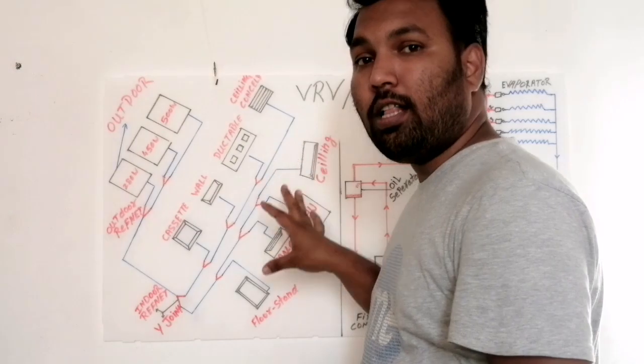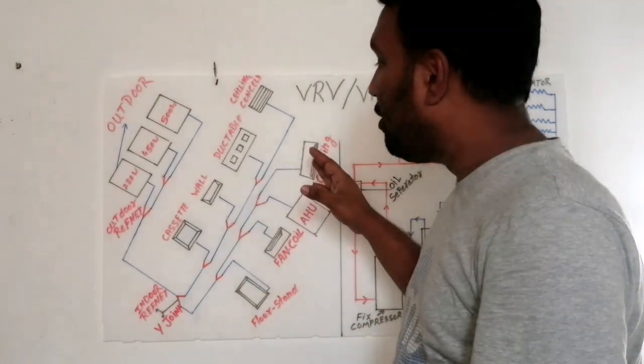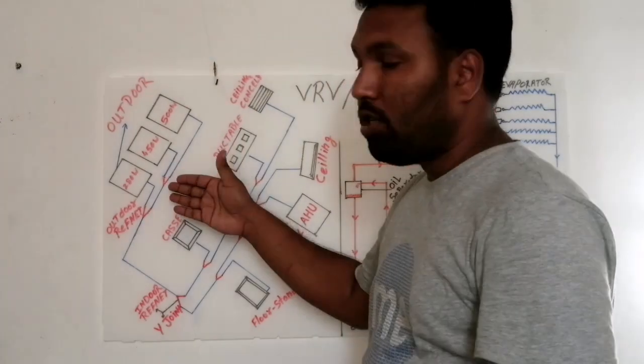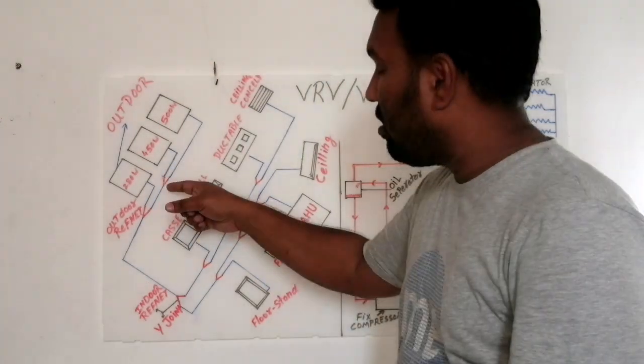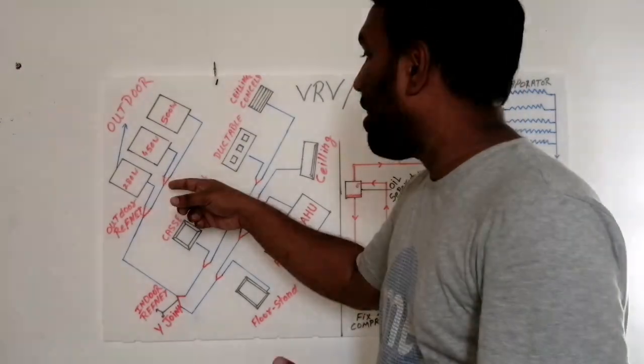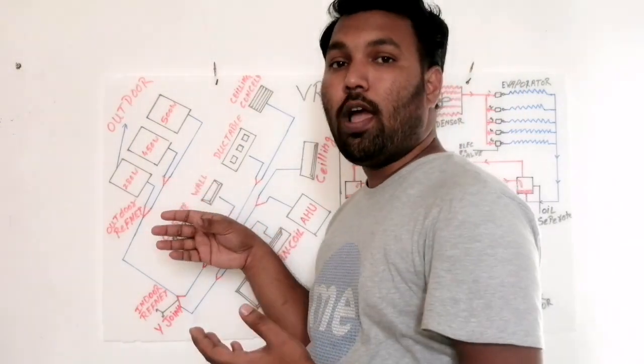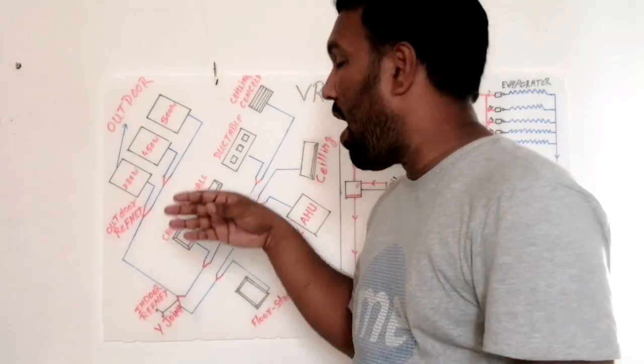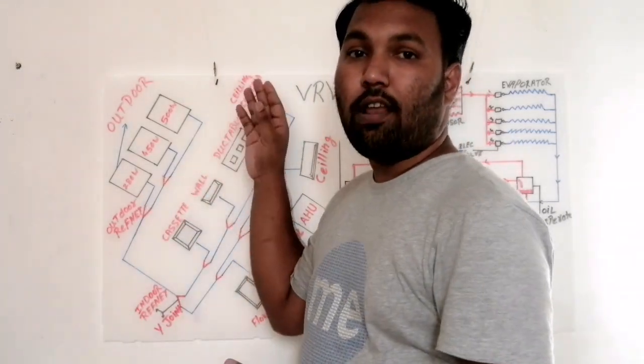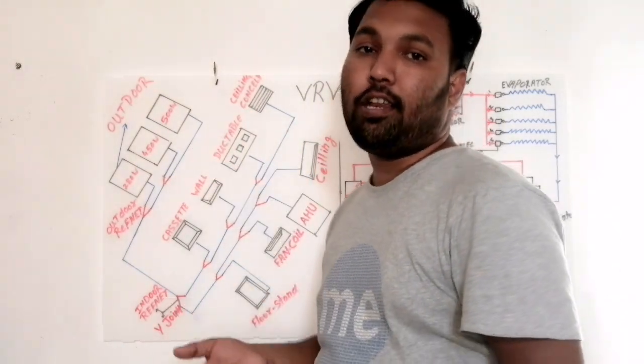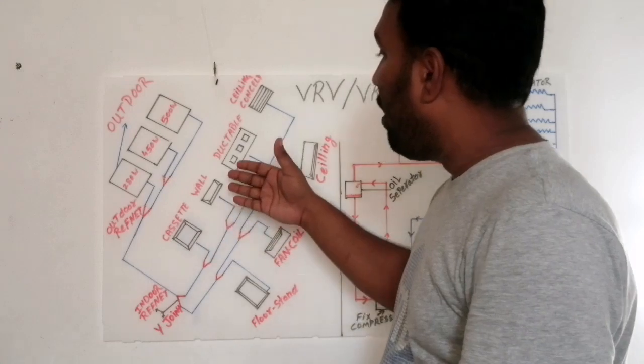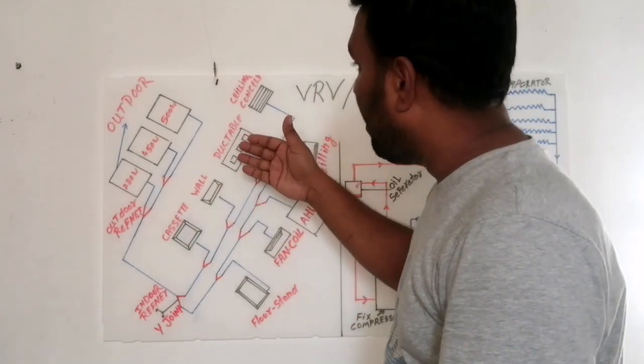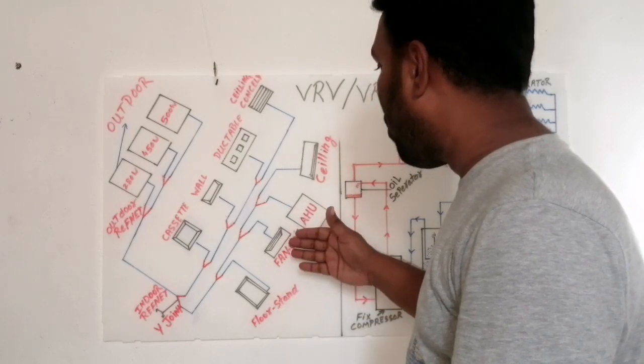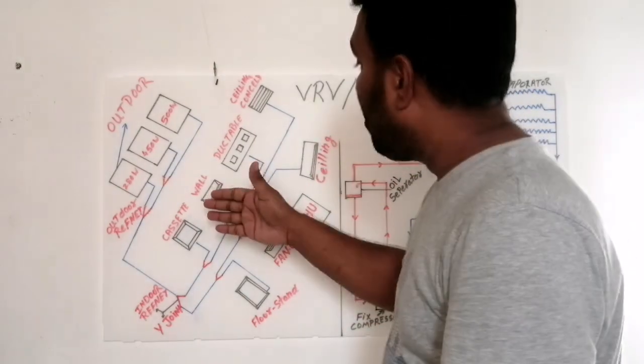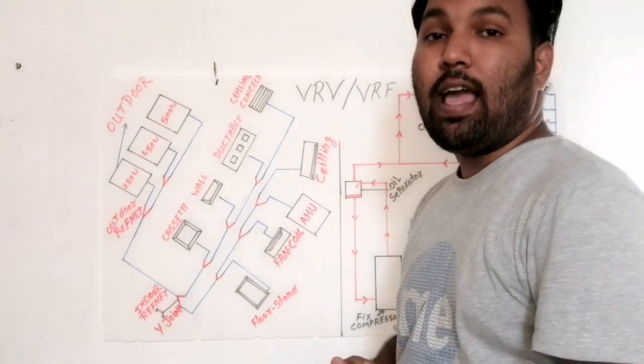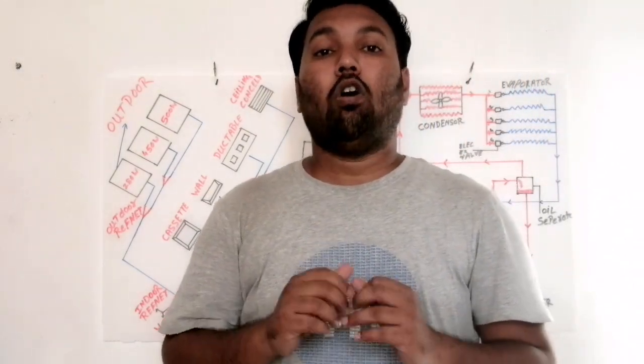The main component which helps the VRV separate all the indoor and outdoor units is the Y joint, or ref net, or distributor. You can see here, this is the Y joint, ref net or distributor. It can easily be placed between each of the indoor units, so we can increase our indoor quantity: we go on doing the piping, put in another Y joint, and again increase our indoor units. You can see the different types of indoor units, like cassette, wall mounted, ductable, ceiling concealed, floor standing, fan coil, AHU and ceiling type. These are the different types and models of indoor units which we can connect to a single VRV or VRF system.